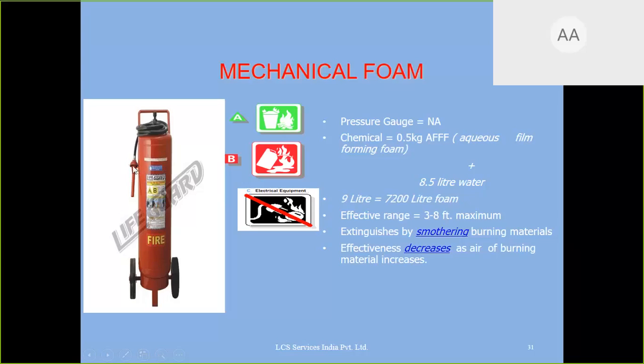When you operate this foam, in the nozzle there is a venturi. When the water pressure is coming out, it will suck air, and the air will mix with this chemical, and then it will become the foam. I will show you the video in the next slide. So this mechanical foam can be used for B class fire. B class is which fire? Liquid. But it cannot be used for C class fire because C is electricity. In electricity, we cannot use water, and it has 8.5 liters of water. Mechanical foam is very, very effective for B class fire. HSD, petrol, diesel, paint, thinner, everywhere mechanical foam is used, which will put a layer on the fire and it will control the fire.